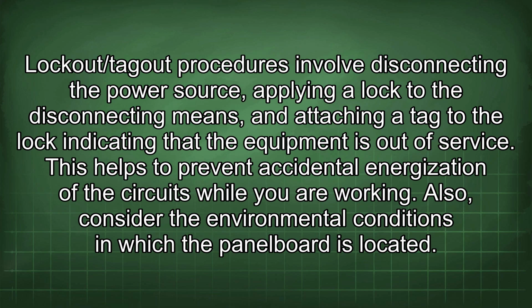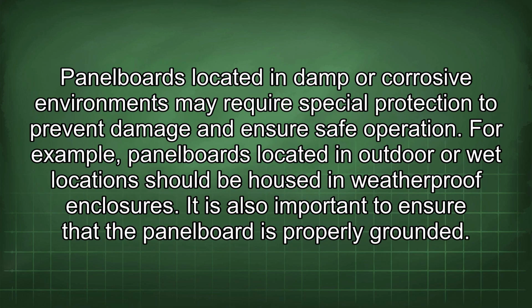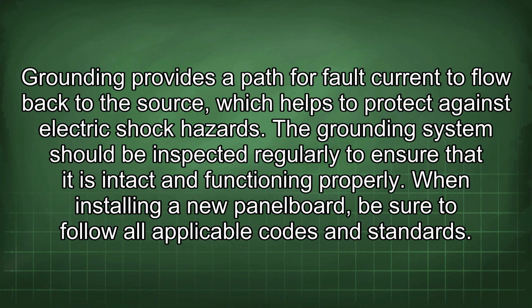Also, consider the environmental conditions in which the panel board is located. Panel boards located in damp or corrosive environments may require special protection to prevent damage and ensure safe operation. For example, panel boards located in outdoor or wet locations should be housed in weatherproof enclosures. It is also important to ensure that the panel board is properly grounded. Grounding provides a path for fault current to flow back to the source, which helps to protect against electric shock hazards. The grounding system should be inspected regularly to ensure that it is intact and functioning properly.